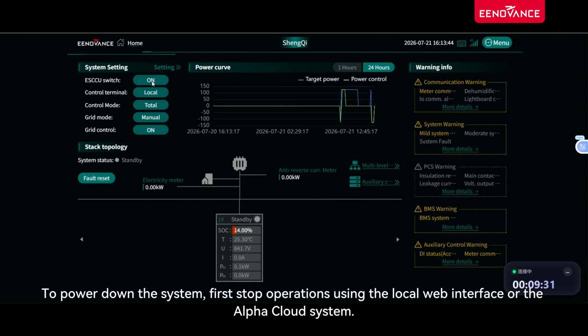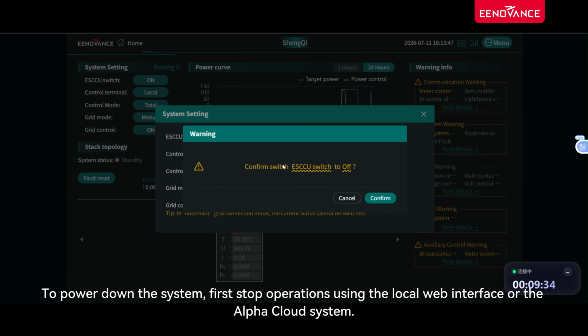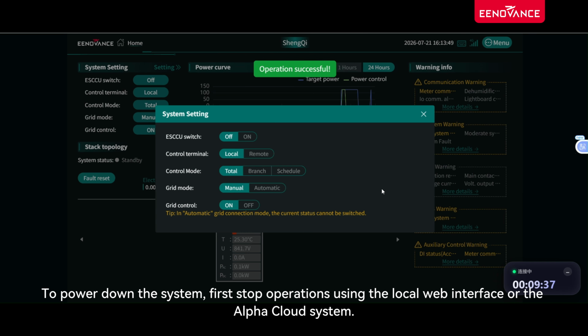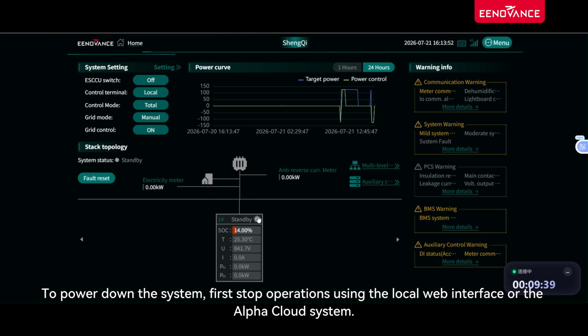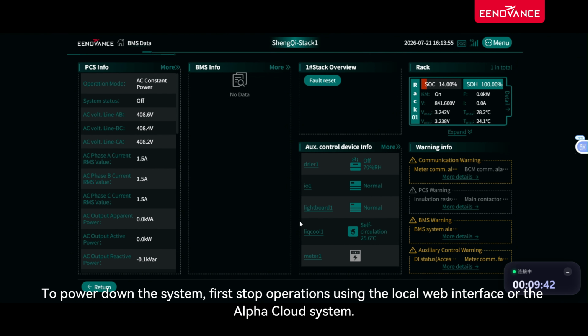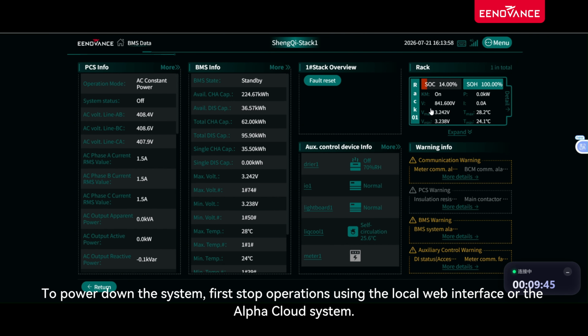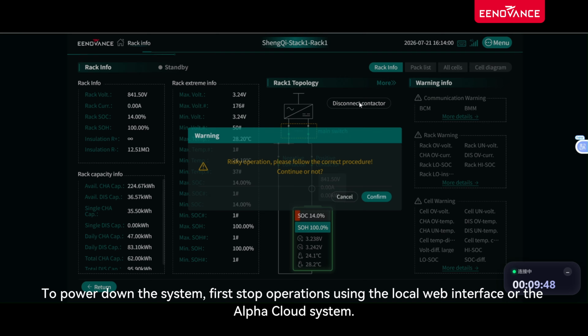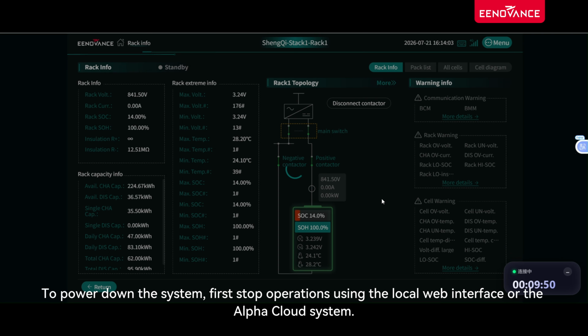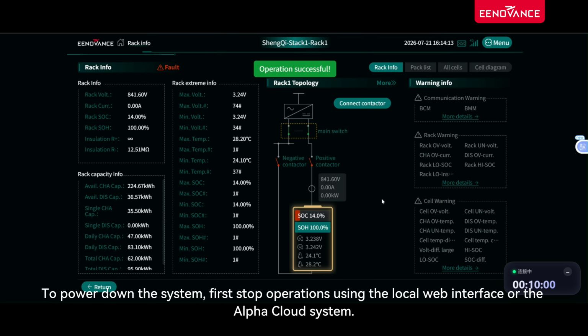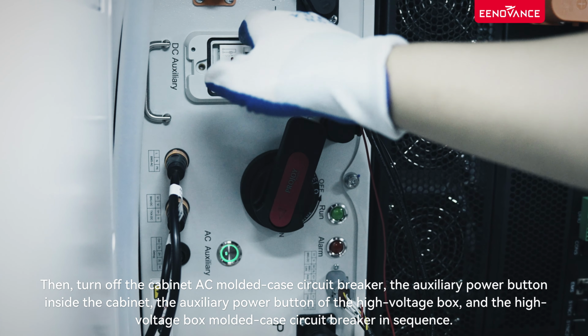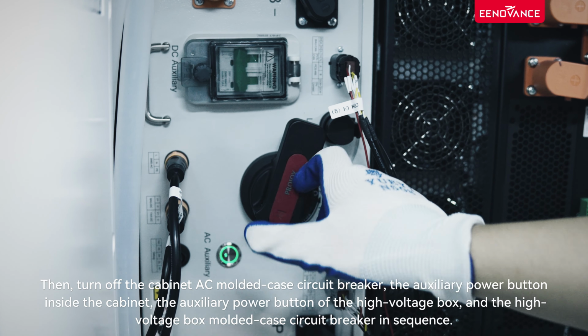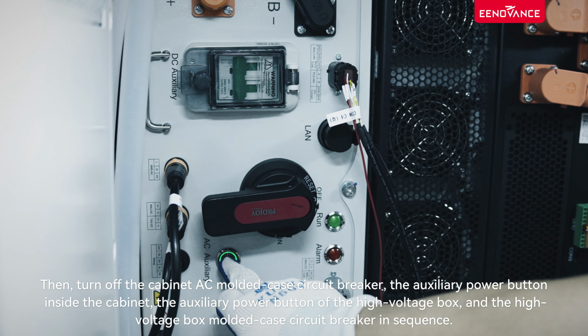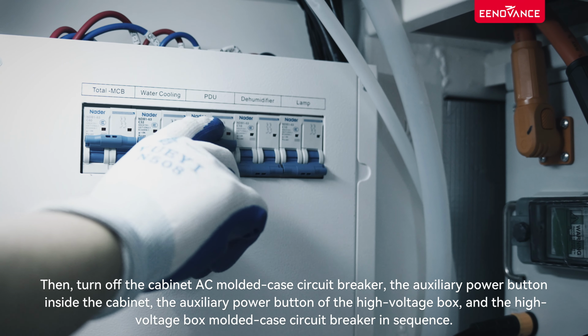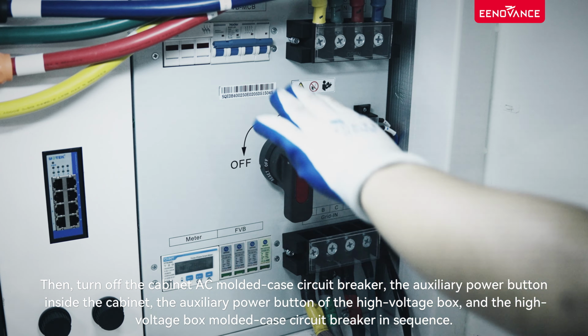To power down the system, first stop operations using the local web interface or the Alpha Cloud system. Then turn off the cabinet AC molded case circuit breaker, the auxiliary power button inside the cabinet, the auxiliary power button of the high voltage box, and the high voltage box molded case circuit breaker in sequence.